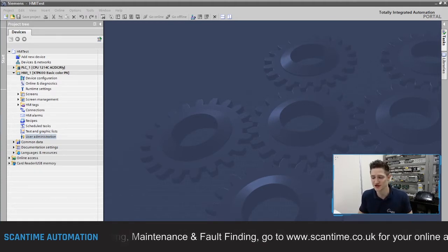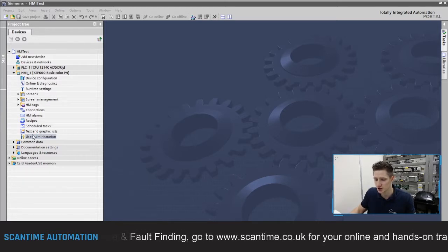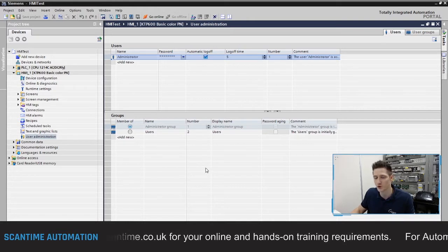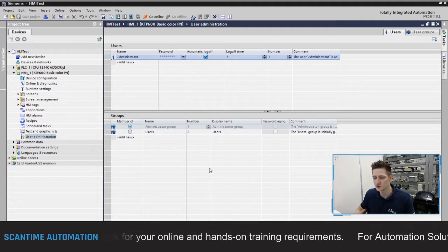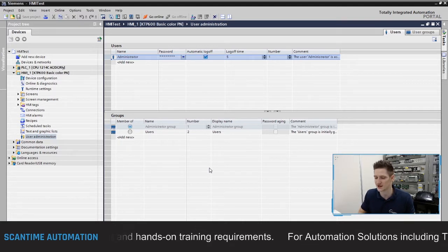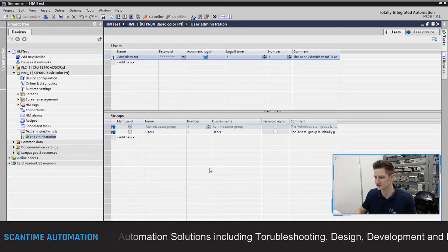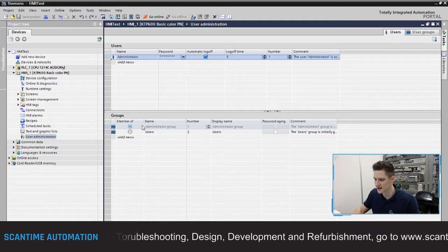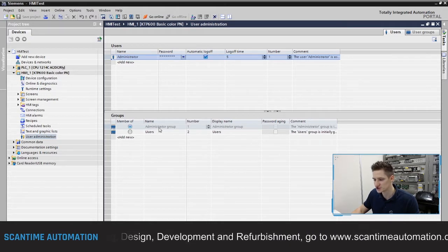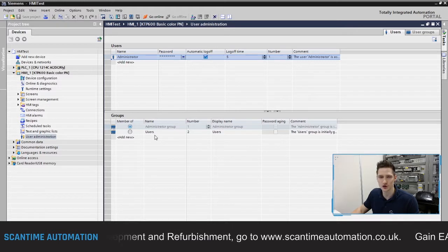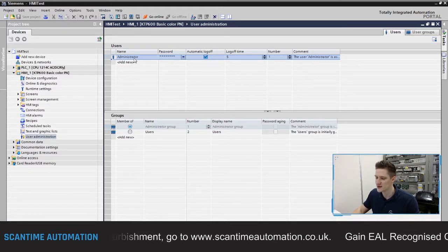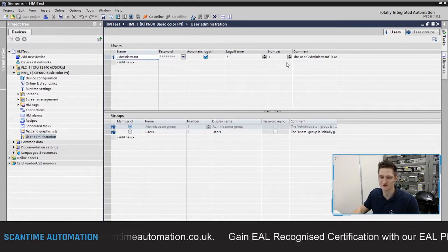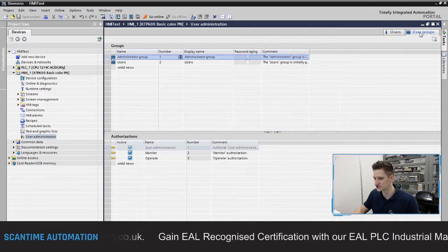Inside WinCC, we go to User Administration and double-click it. This pops up with a default setup already configured by Siemens, which you can change however you want. There are two tabs: the User tab and the User Group tab. By default, two groups are already set up: Administrator Group and User Group. You can also see the individual users that have been set up, along with their passwords and settings.